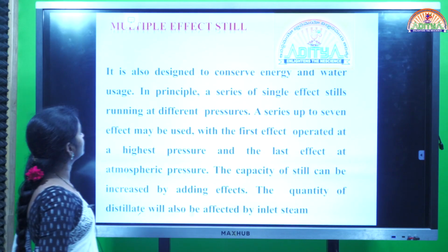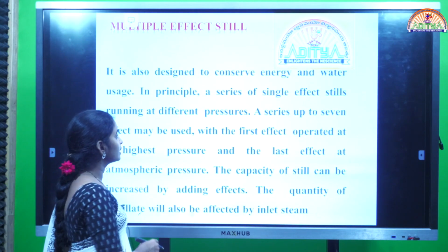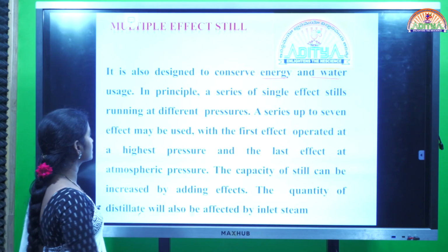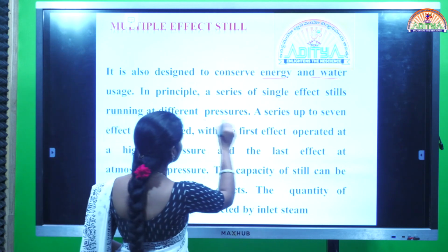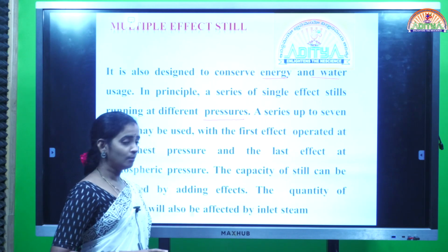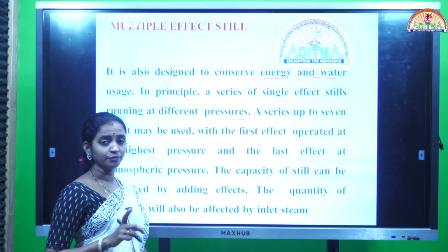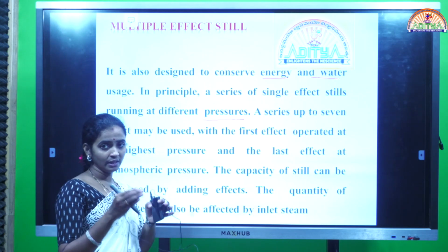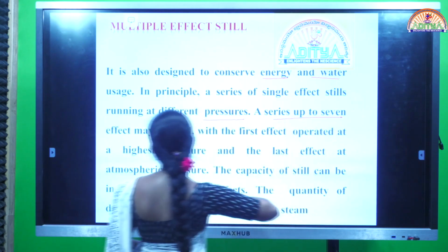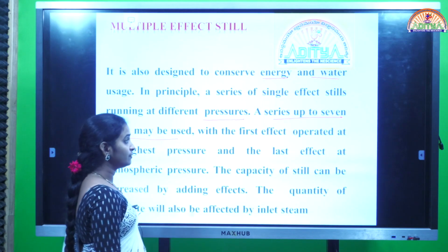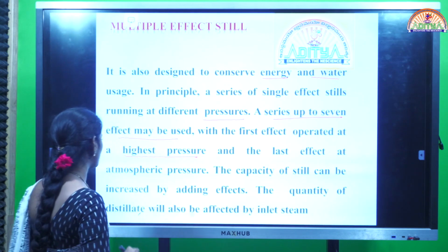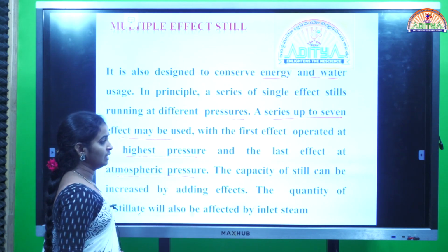And coming to the principle, it is designed to conserve energy and water. In principle, it is a series of single effect stills running at different pressures. I said that all the stills are serially connected one by one, but those stills are running at different pressures, not at the same pressure. Each chamber has a particular pressure. A series of up to 7 effects may be used, with the first effect operated at the highest pressure and the last effect operated at atmospheric pressure.